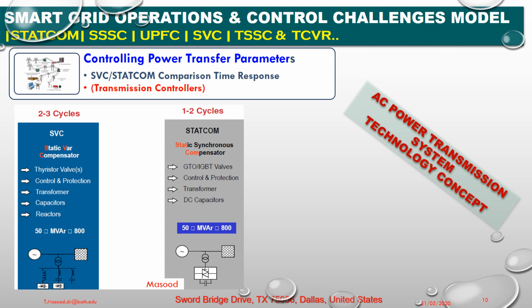As we see, STATCOM comparison time response. If you can see here, the SVC, thyristor based switch devices, and this is my converter based devices. The SVC normally operates within 2 to 3 cycles, and STATCOM operates in 1 to 2 cycles. So both have different configuration: thyristor switches, control protection, transformer, capacitor, reactors, and here we use IGBT, control protection, transformer and DC capacitors. So that is how they both are responding. In the next slide we will demonstrate the compensator factor or V and I characteristic, how the SVC and STATCOM are functioning.